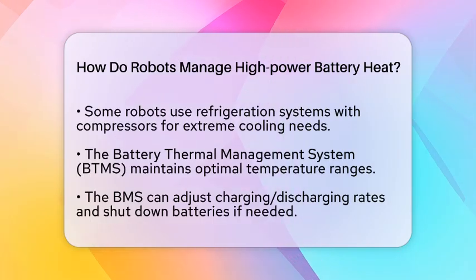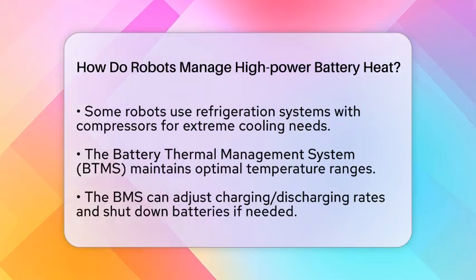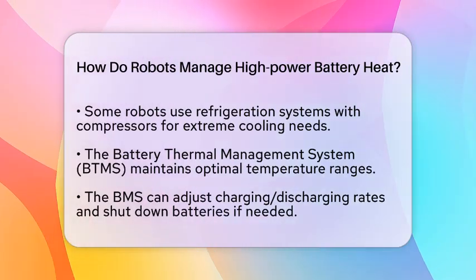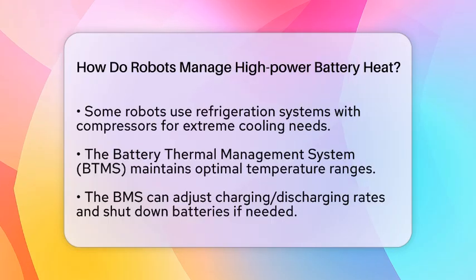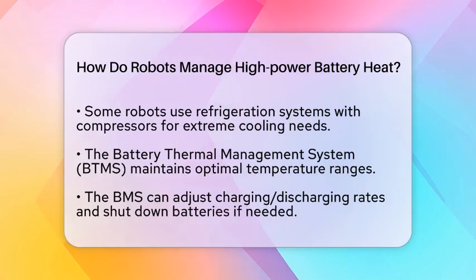A battery thermal management system, or BTMS, combines sensors, cooling parts, and control electronics. It keeps the battery temperature within a safe range, usually between 20 and 45 degrees Celsius. In cold weather, it can even warm the batteries with heating elements to make sure they charge and work properly.